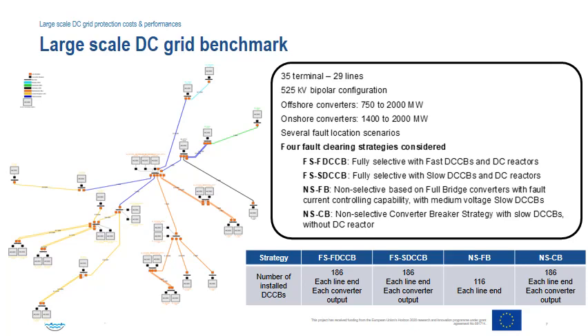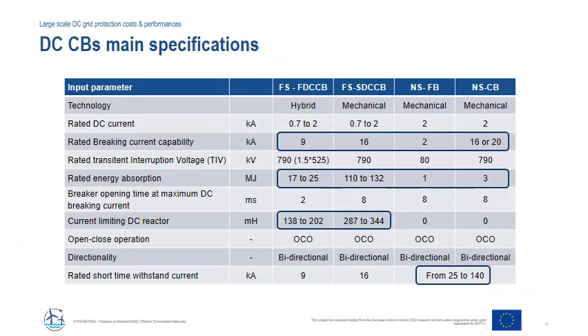Note that all proposed strategies lead to a quite high number of DC circuit breakers needing to be installed in order to allow both primary and backup protection sequence. This table gives the DC circuit breakers' main specifications for the four fault clearing strategies. It can be observed that the design of the protection system leads to different specifications and consequently to different costs. More particularly, the presence of a DC reactor with fully selective strategies leads to quite a high level of energy being dissipated by the surge arrestor and to an additional volume and weight for the DC circuit breaker.